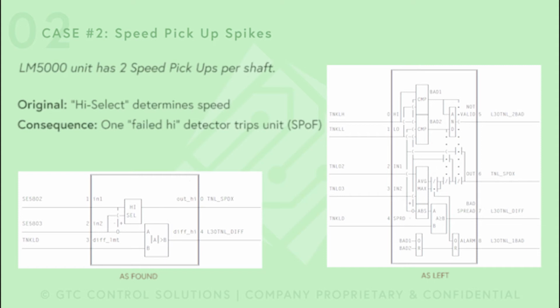In fact, the story goes like this. The customer was starting the unit, no problems. All of a sudden, one of the 2 speed pickups reaches 128%, which is the max scale for speed, if you're familiar with controls. And when reading 128% speed, the protective system says, oh, wait a minute, we have an overspeed trip. And the unit was just cranking. The actual speed of the unit was about 28%. So they had a spike, they tripped. And after the trip, they restarted again. They had to wait, go through a purge. They lost like an hour and again tripped. And eventually, on one of these attempts, the unit would survive the start and go through the normal sequence.